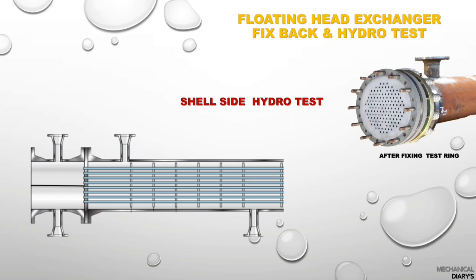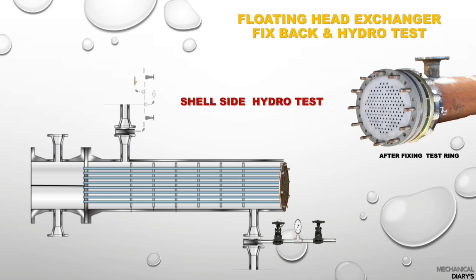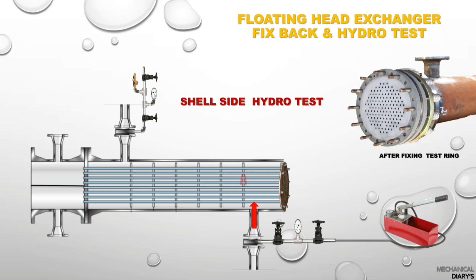Whenever you start boxing up, make sure the gasket area between the tube sheet and shell is very clean. Fix the tube bundle with the gasket, then fix the channel head with its gasket as per your markings. Once the tube bundle and channel head are fixed, go to the back side — the floating head area. A test ring is needed here because the floating head cannot be fixed for shell-side testing.